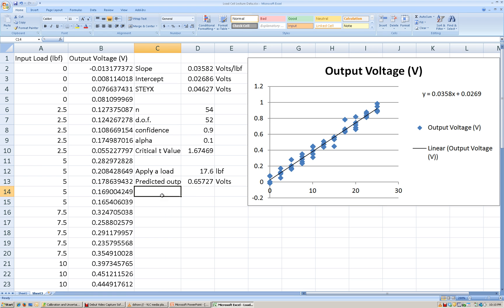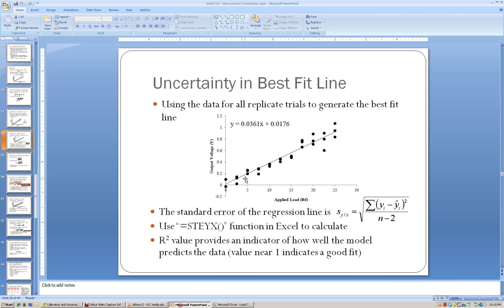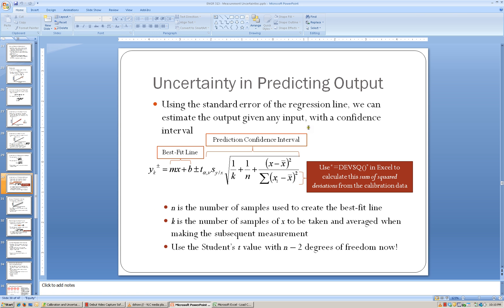We should get a voltage of 0.657 volts out of the load cell if we apply 17.6 pounds-force to the input. Now the question we're really working towards is: what is the 90% confidence limit going to be on this output value? In order to do that, we're going to go back to the equation for predicting the output based on our input. We have the T critical value and our standard uncertainty value. Now we need to calculate what's under the radical.